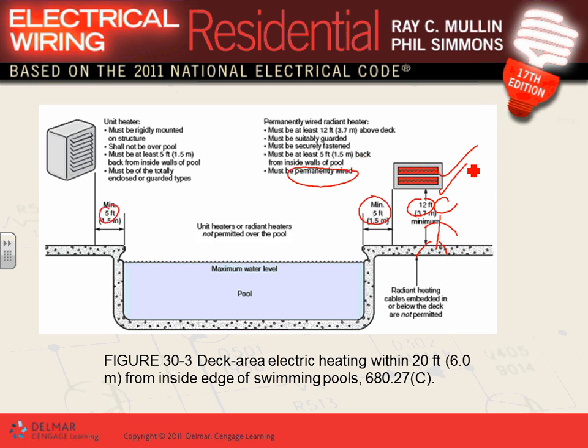Same thing for the unit heater. If you have a unit heater, it must be mounted. You have to move it away 5 feet. It must be rigidly mounted and set back 5 feet. It must be of the totally enclosed or guarded type. This type of unit doesn't have to be elevated, but you have to move it 5 feet away.